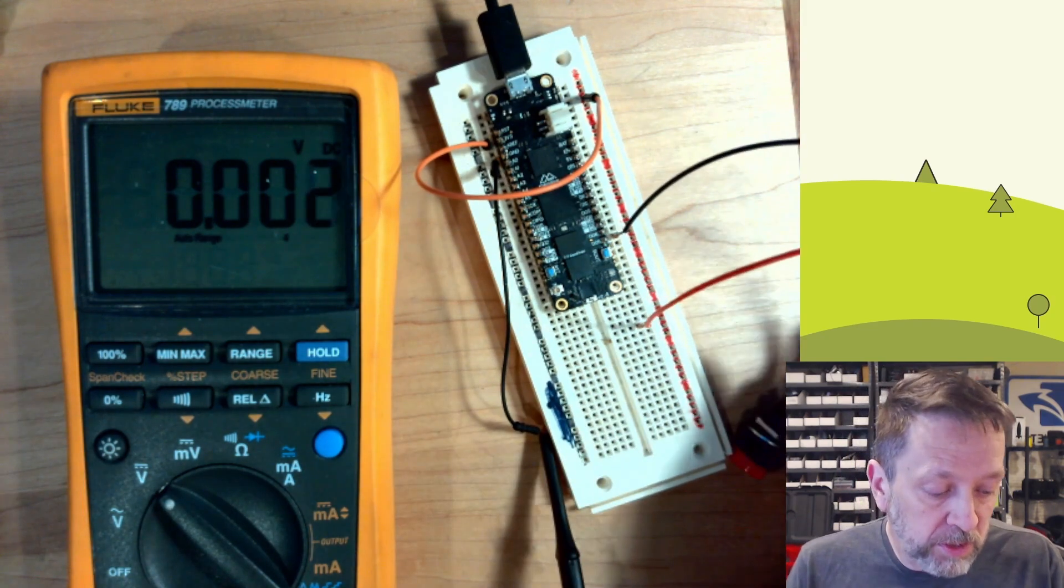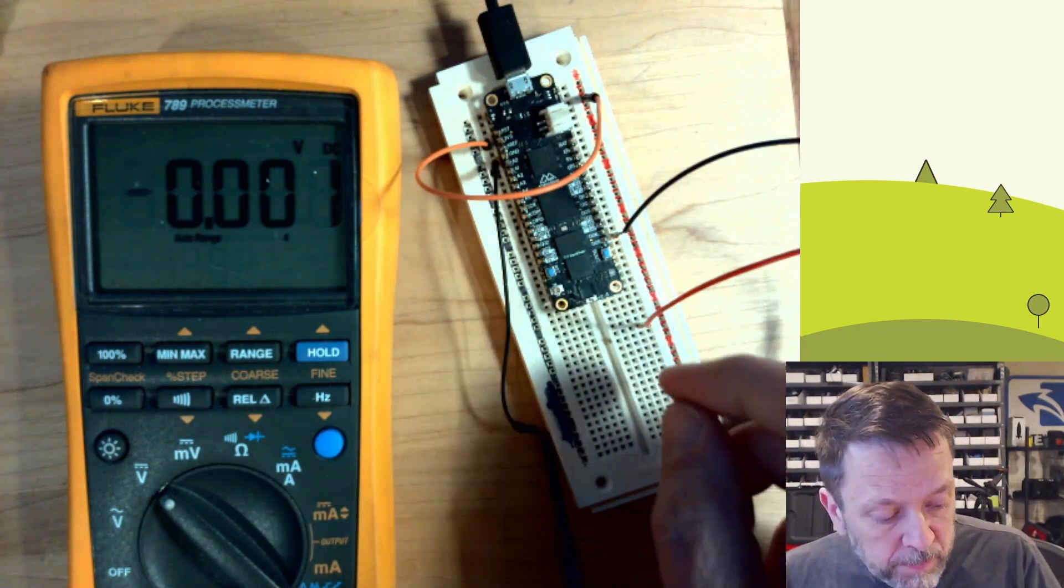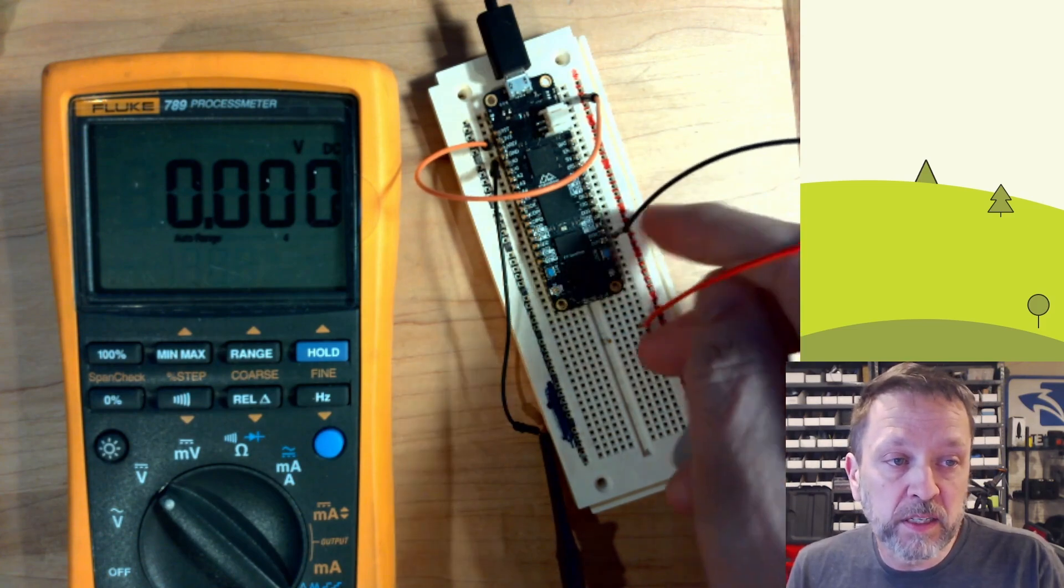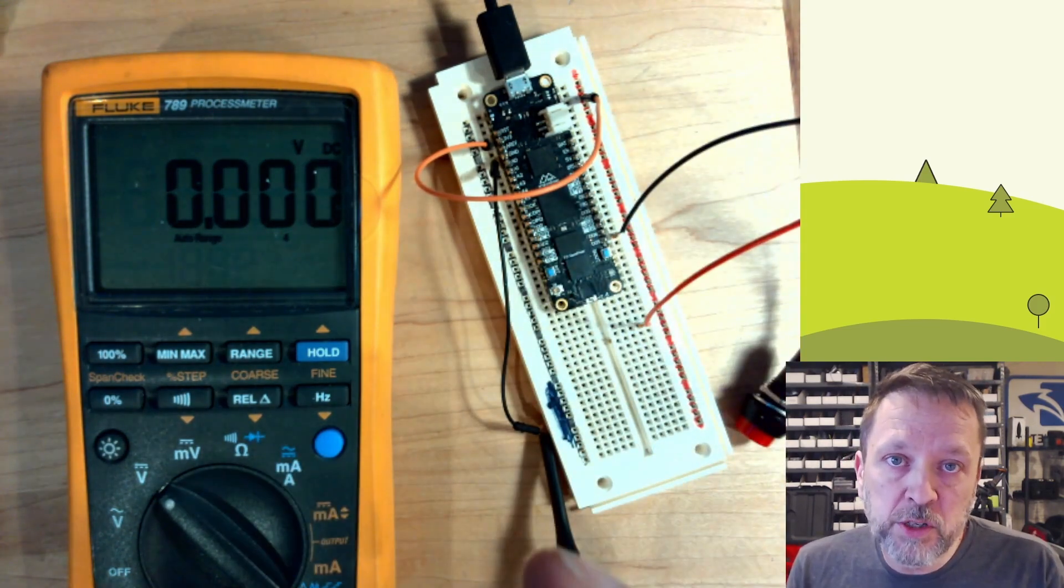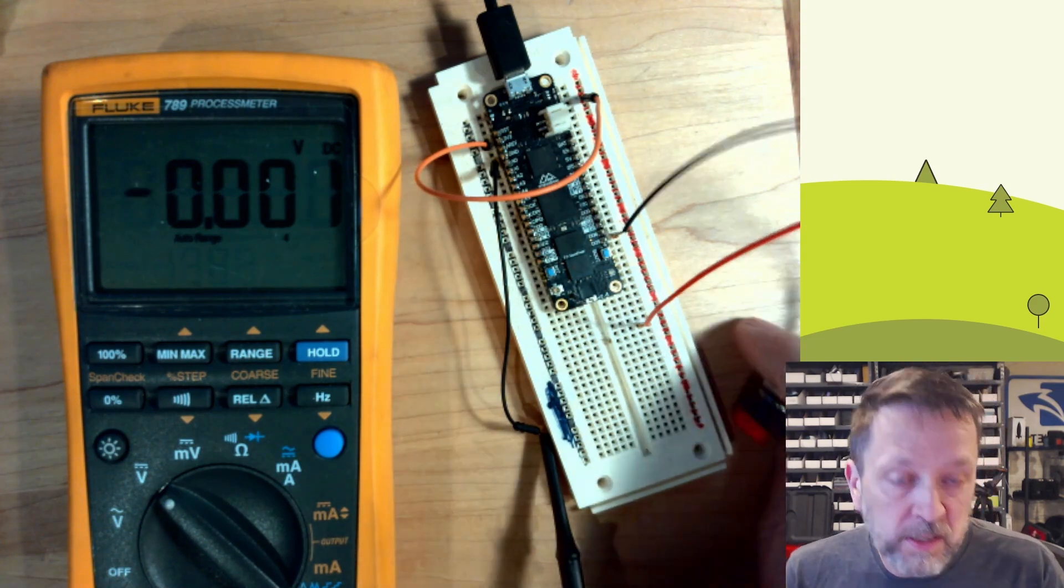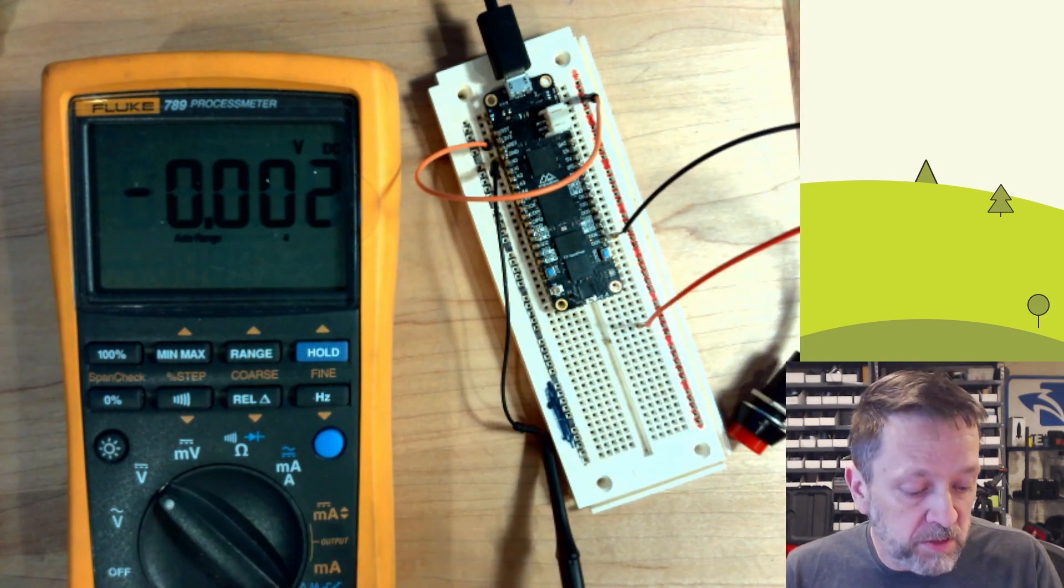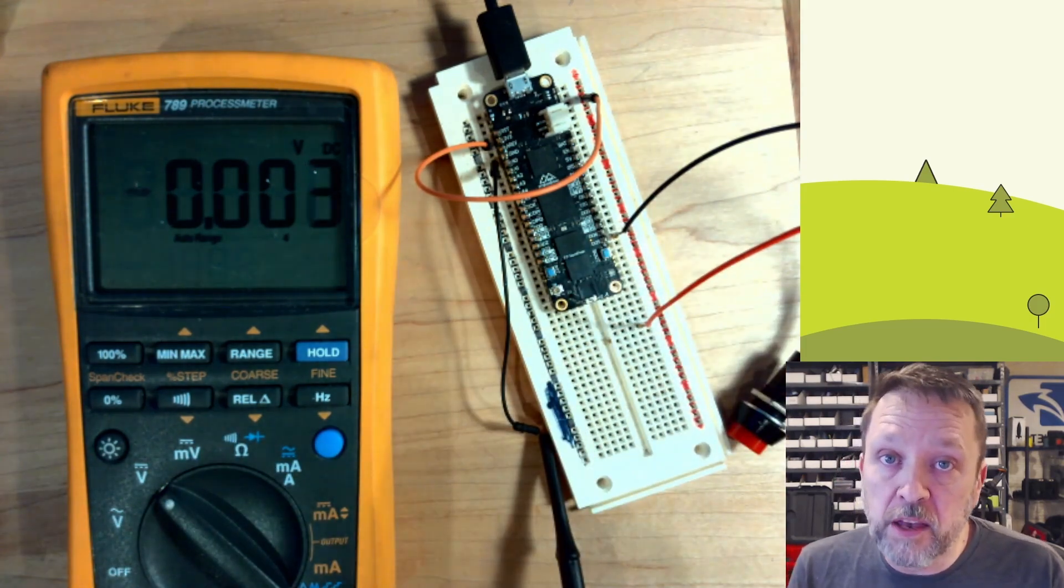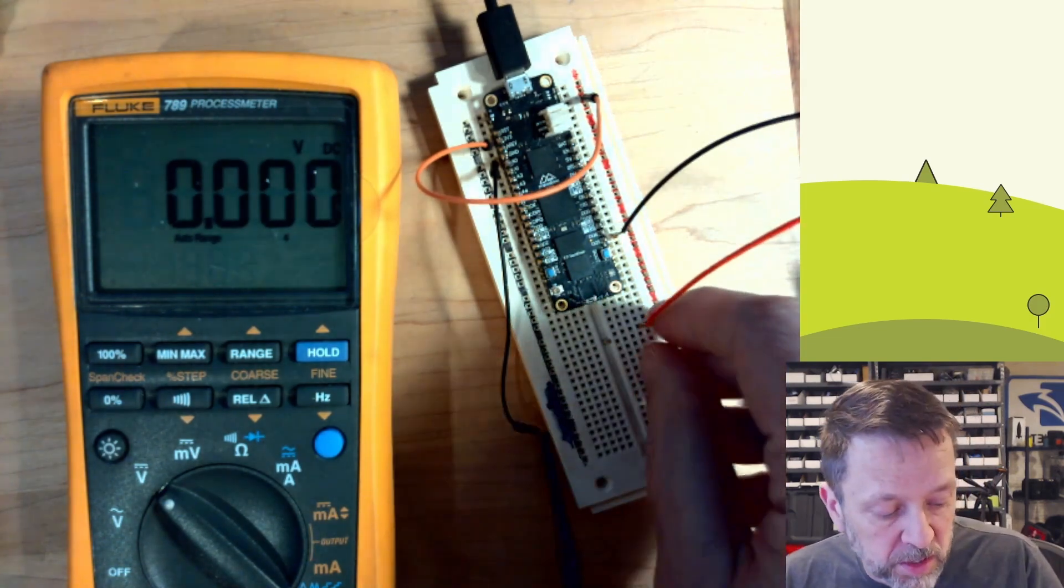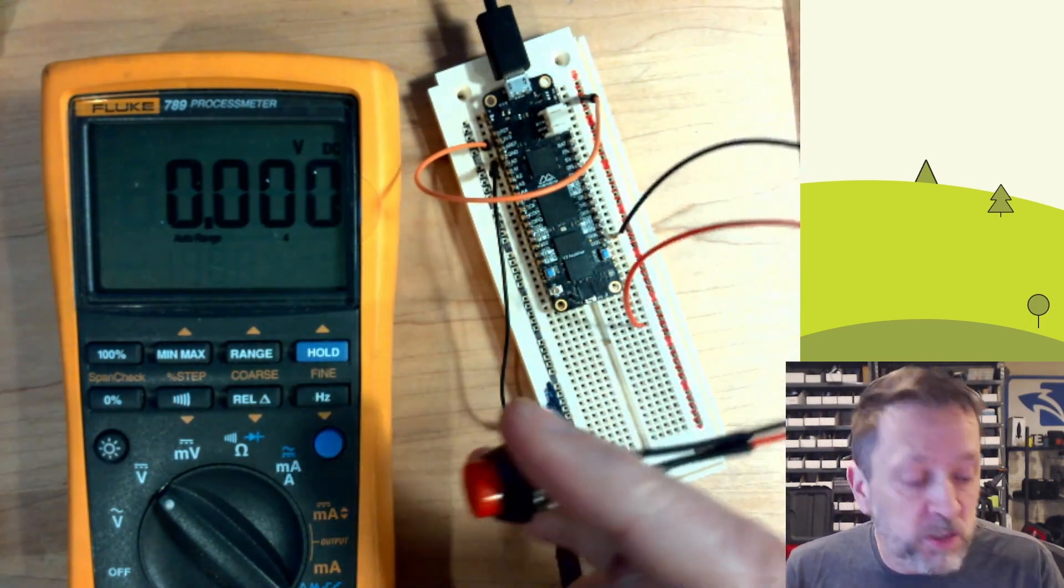Now, what I would do typically is I would look at the wires here. And if this was connected to positive here and this is connected, and when I click it, I don't see voltage. That would be really suspicious that the switch itself is bad. You could use your meter and use the ohm setting and ohm the switch out just to see if when you connect it, it doesn't do what it's supposed to do. So now let's assume that we figure out that it's a bad switch.